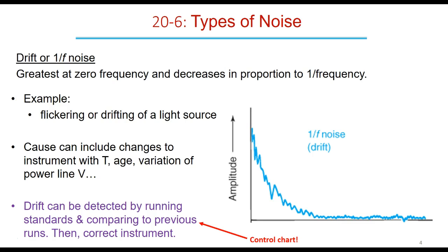You want to actually see how it's responding over time, because your conditions in your instrument and what you're doing with it might be different from your manufacturer's. So you're going to want to run those standards, assemble a control chart, and see when this drift starts to occur. When do you start getting deviations from the values you expected when everything was sparkling and new?